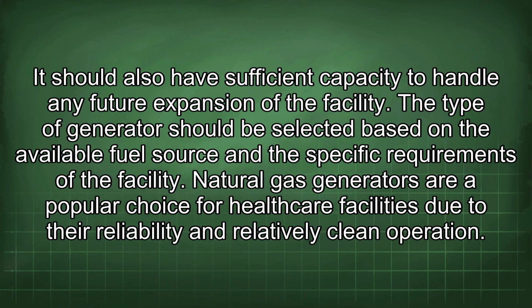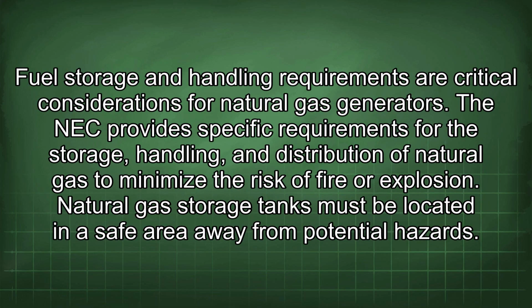The type of generator should be selected based on the available fuel source and the specific requirements of the facility. Natural gas generators are a popular choice for healthcare facilities due to their reliability and relatively clean operation. Fuel storage and handling requirements are critical considerations for natural gas generators. The NEC provides specific requirements for the storage, handling, and distribution of natural gas to minimize the risk of fire or explosion. Natural gas storage tanks must be located in a safe area away from potential hazards.